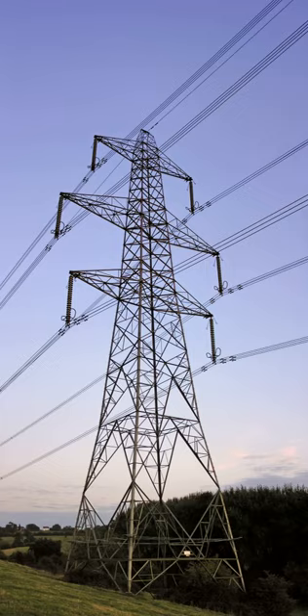Tower structures can be classified by the way in which they support the line conductors. Suspension structures support the conductor vertically using suspension insulators. Strain structures resist net tension in the conductors and the conductors attach to the structure through strain insulators. Dead-end structures support the full weight of the conductor and also all the tension in it, and also use strain insulators.